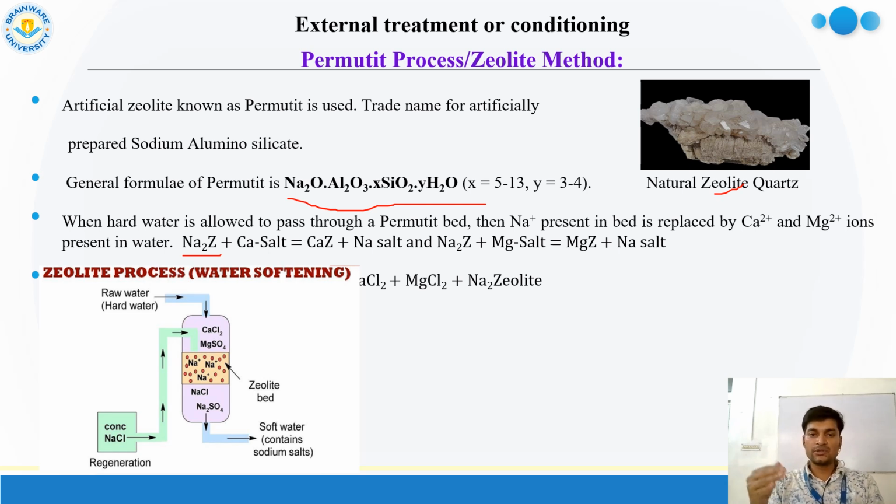So that sodium zeolite is converted into calcium magnesium zeolite, and sodium salt is forming, and sodium salt is not responsible for any type of harmful effect on the boiler. So this is the process.